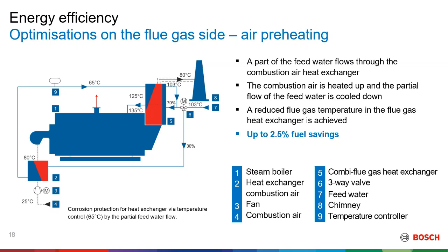Another loss that you're going to look at later on is that by increasing the temperature of the air that is flowing into the boiler, you reduce the amount of losses that you get during the purging process when the boiler is starting up and so on. So therefore, you'll be saving around 2% of fuel just by preheating the air that is flowing into the burner. Okay, next slide.